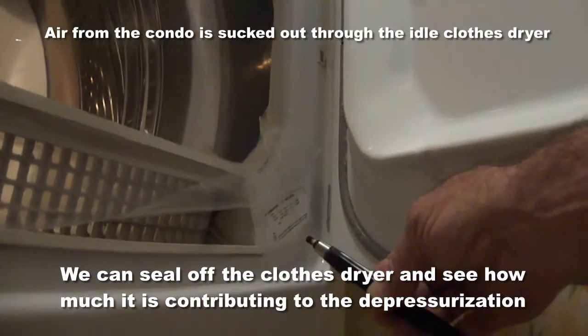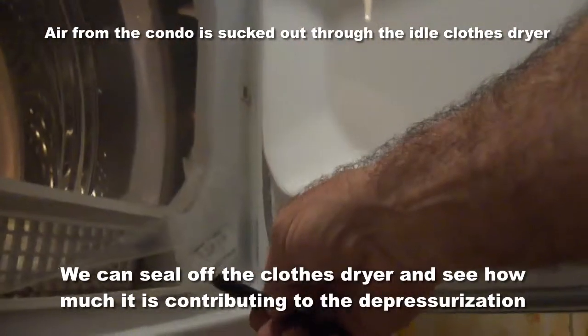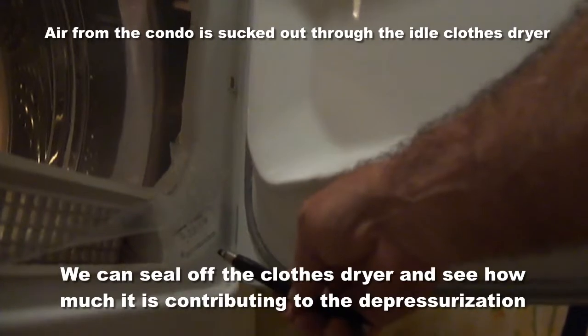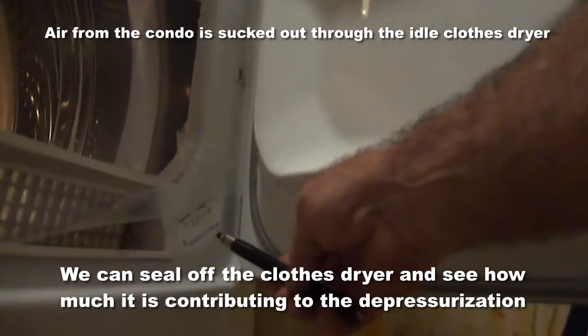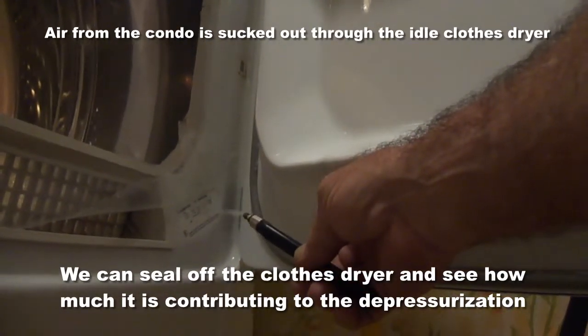This happens even when the dryer door is shut, because it's open on a screen on the other side. That is the thing causing the moisture to come into the condo. The ventilation itself does not cause mold — it's the humid air that replaces the dry air we're pulling out that is causing the mold. Until the building is fixed, the only thing we can do is run dehumidifiers to try to mop it up. We can't keep it from coming in, but you can seal the vent when you're away to eliminate that source.